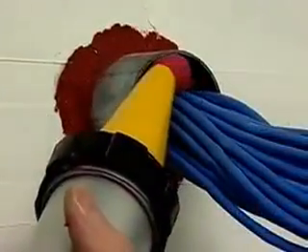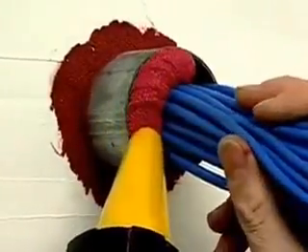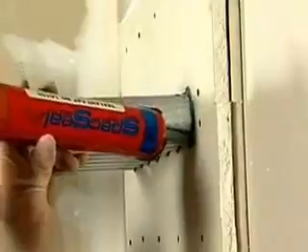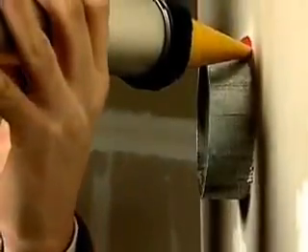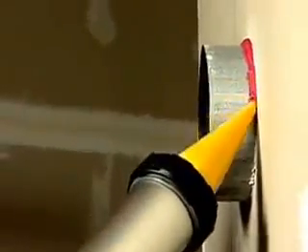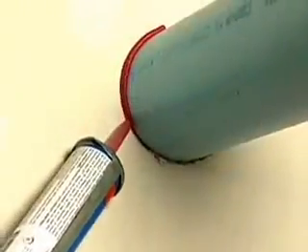The most common mistake made is that Firestop sealant is generally caulked around a penetration with little or no regard to the type of penetration being sealed. While a relatively small bead of Firestop sealant may be adequate for a metallic pipe, smearing a thin film of caulk around a large plastic pipe or bundle of cables simply won't work.